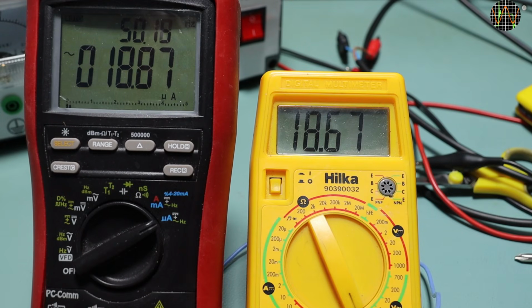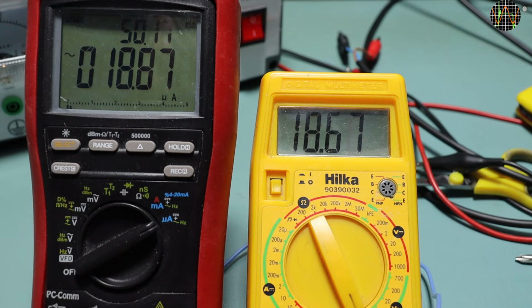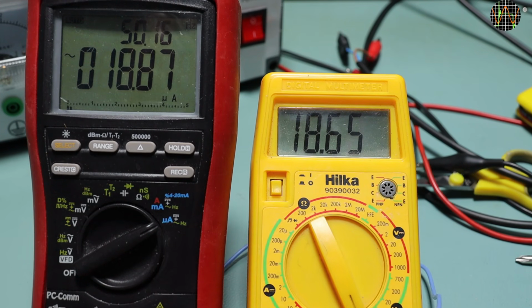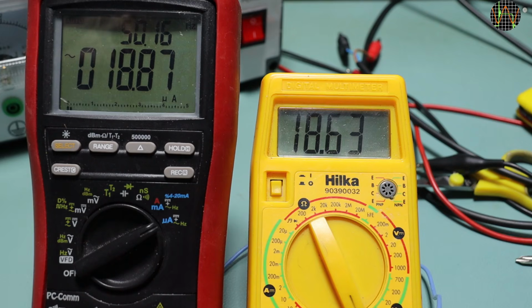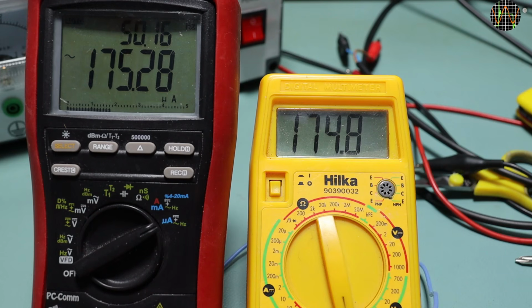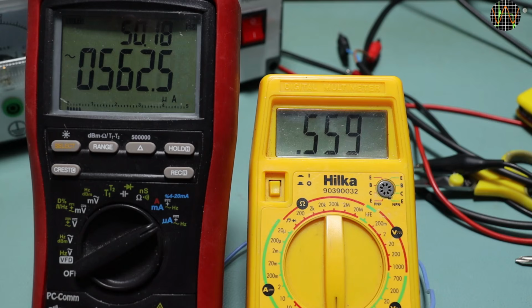Testing AC amps. For microamps and milliamps, I use again a function generator set to sine wave at about 50 Hz, feeding a 50 ohm load with the meters connected in series to measure the current, but I'm not bothering dialing in nice test values. Starting with about 19 microamps in the 20 microamp range, and both meters read very close. About 175 microamps in the 200 microamp range, and again very close. Same for about 560 microamps in the 2 milliamp range.